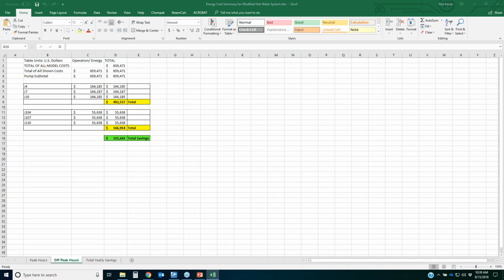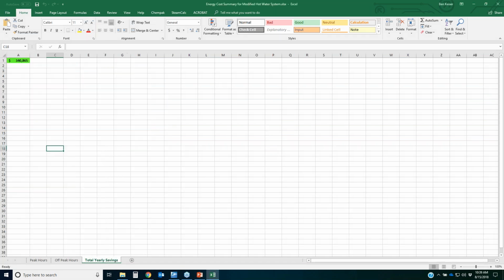Off-peak hour operation, this is significant. So here you're looking at almost $500,000 a year in energy costs using control valves versus $167,000. So you've got $326,000 in annual savings by switching to a variable speed drive. Much, much better operation. You've got some significant operating savings there. Total of $341,000 when you add the peak time and off-peak time together. But ultimately, your pumps are operating much more efficiently, 95% of their best efficiency points. You're going to be avoiding those issues.